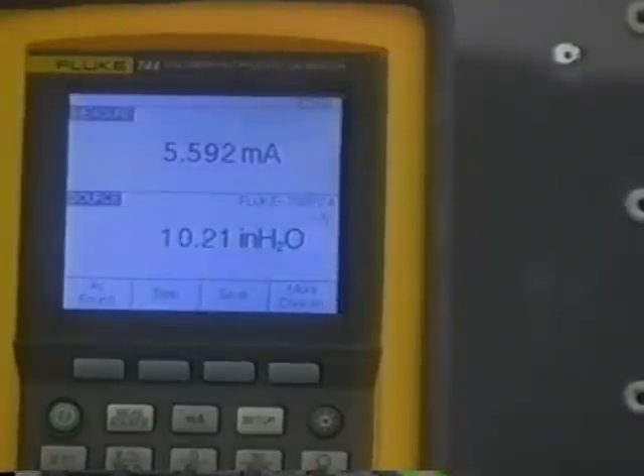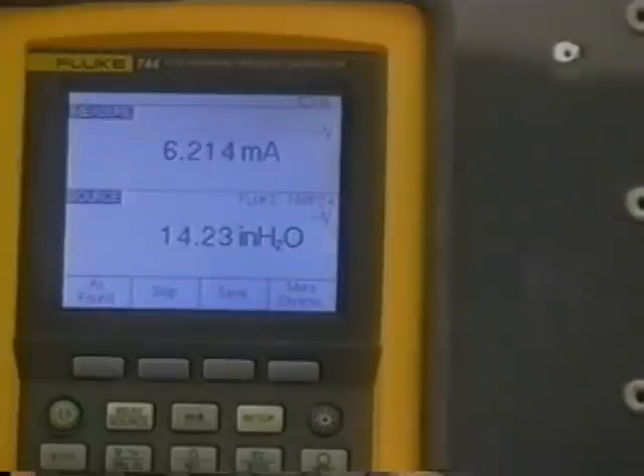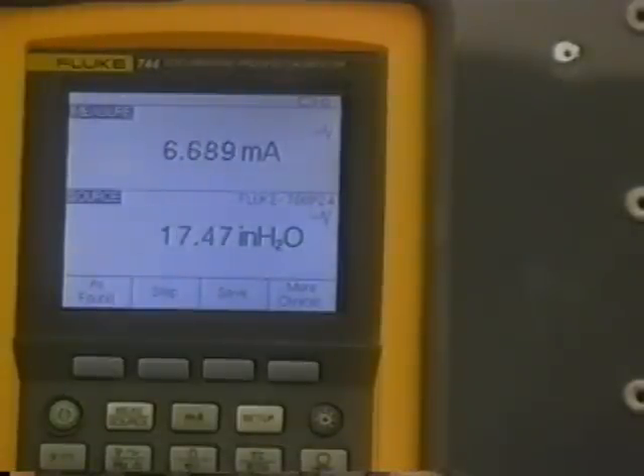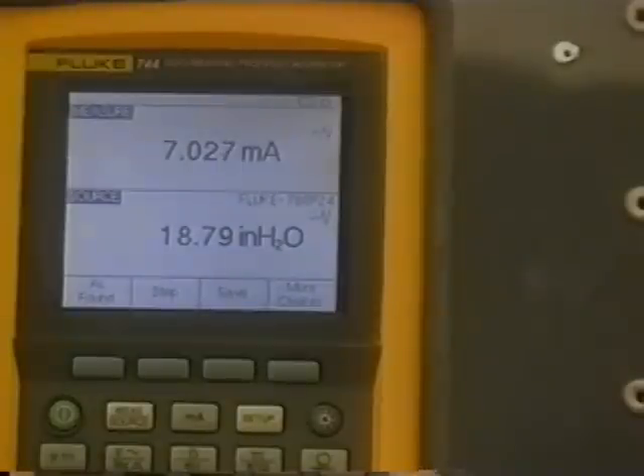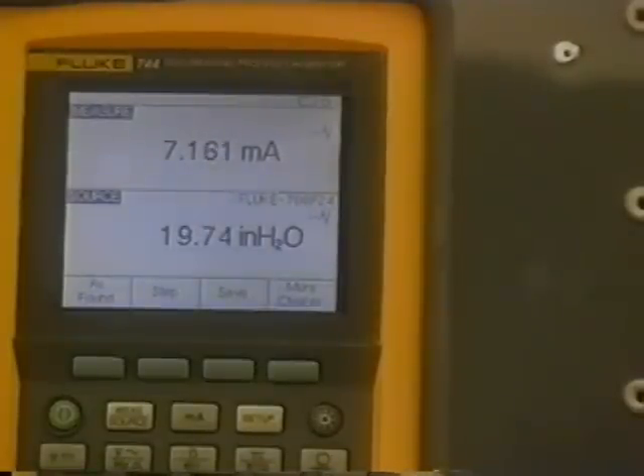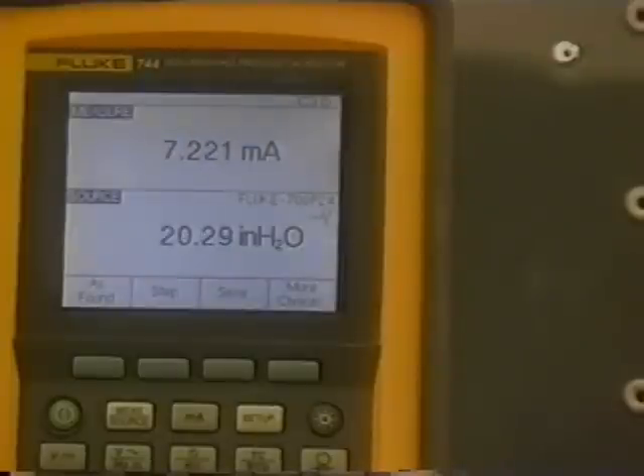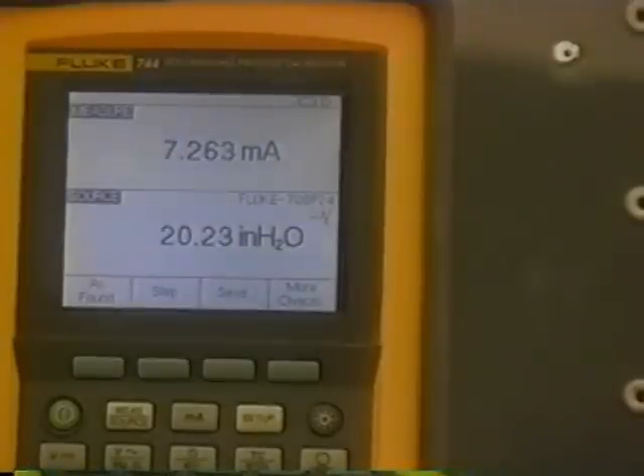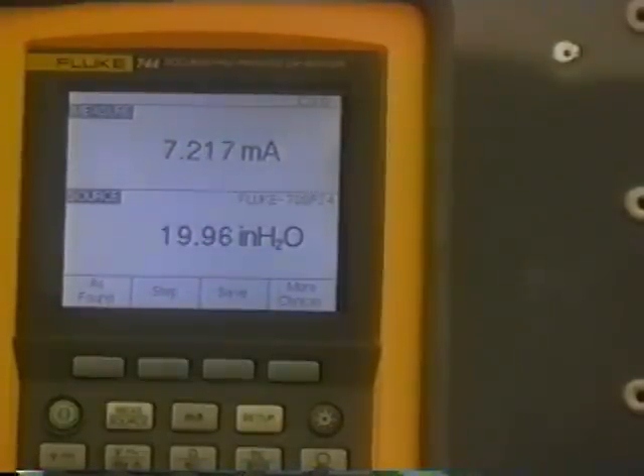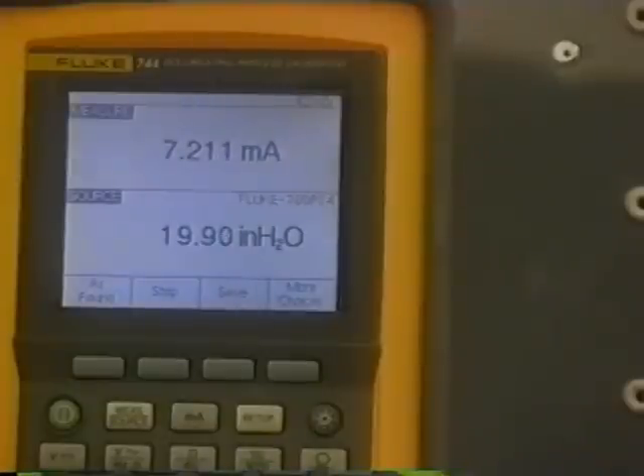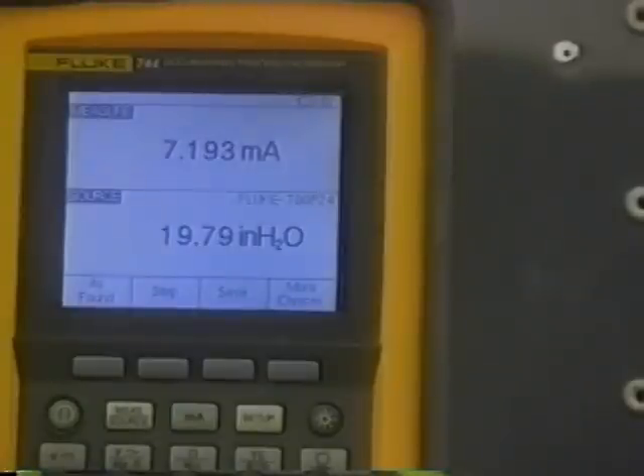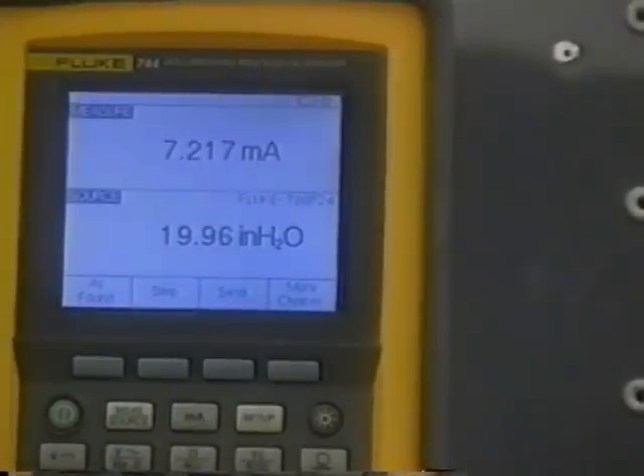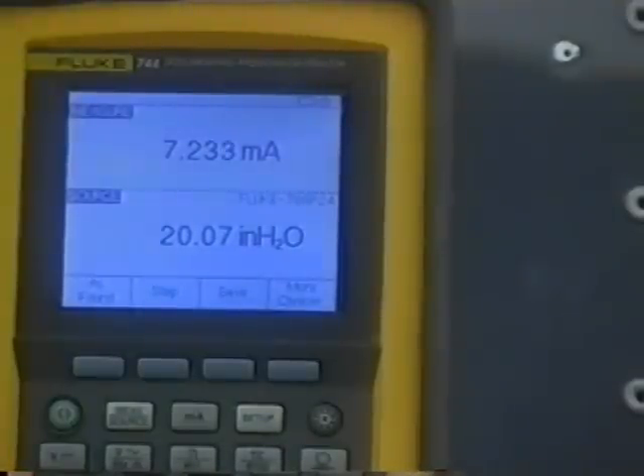If I dial it up to 20%, 20 inches of water. 20.04 inches of water. Let's see that we've got, 7.23 milliamps.